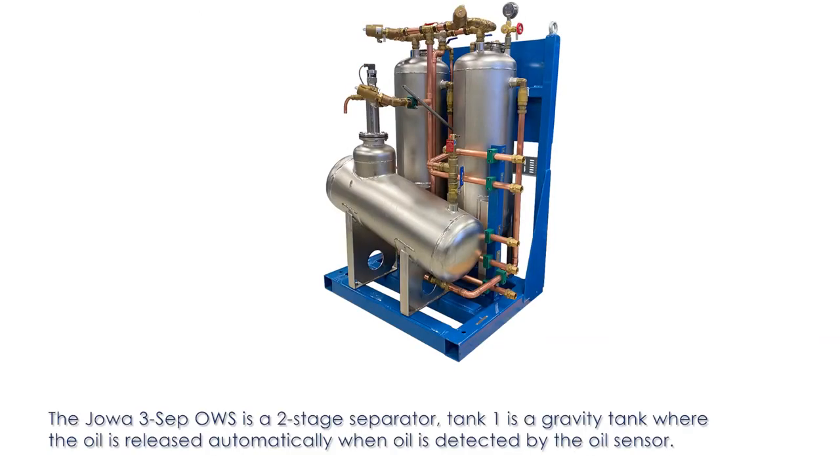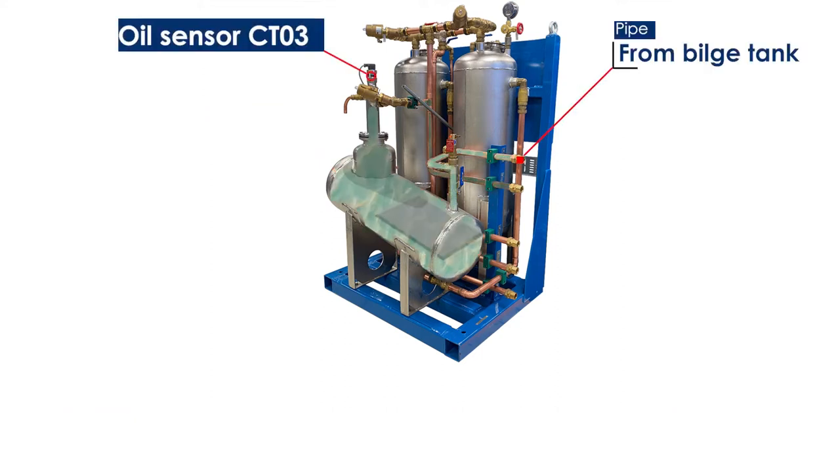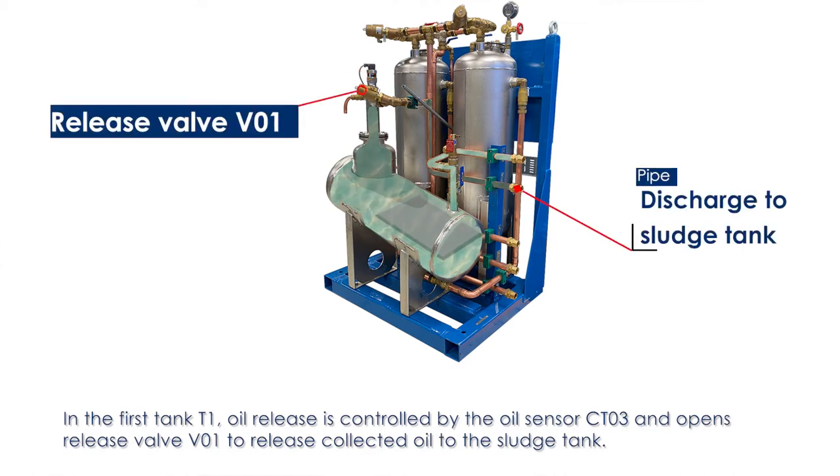The Jowa 3-Sep OWS is a two-stage separator. Tank 1 is a gravity tank where oil is released automatically when oil is detected by the oil sensor. In the first tank, T1, oil release is controlled by the oil sensor CT03, which opens release valve V01 to release collected oil to the sludge tank.